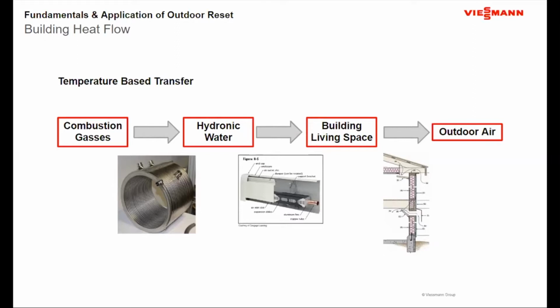And we really need to have a look at how outdoor reset fits into this, from the aspect of comfort and also from an efficiency standpoint. Now, when we look at this process, there are a couple of points here that normally are, I'm going to call them, fairly close to anchored. So if I'm burning natural gas, my combustion temperature is going to be somewhere in the neighborhood of about 3,000 degrees. You will see numbers higher, you will see numbers lower as well. It depends on the makeup of the natural gas, because it's not a pure gas, and it also depends on how much excess air is applied to the process.